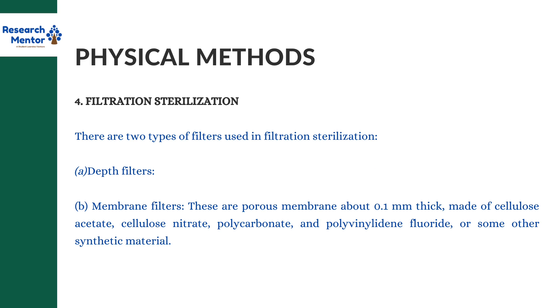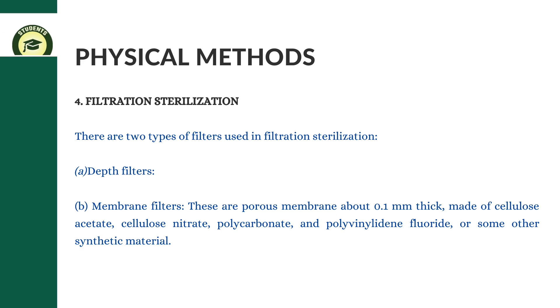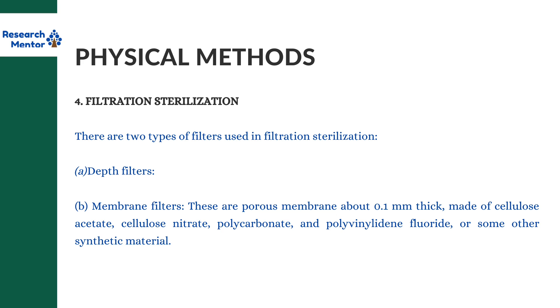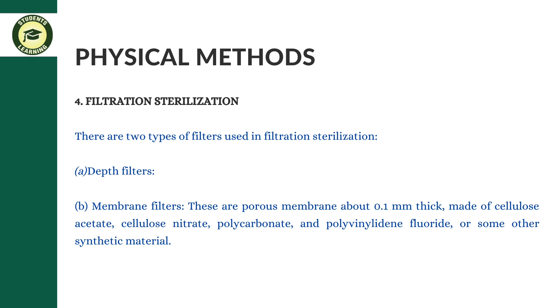There are two types of filters used in filtration sterilization: depth filters and membrane filters. Membrane filters are porous membranes about 0.1 millimeter thick, made of cellulose acetate, cellulose nitrate, polycarbonate, polyvinylidene fluoride, or some other synthetic material.